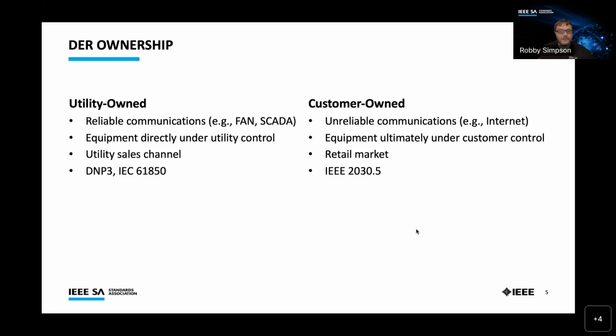And then lastly, the standards and protocols themselves. Usually with utility-owned equipment, often in the US you'll see DNP3. Often in other parts of the world you'll see IEC 61850. There tend to be these protocol standards that are specific for utility networks, for the utility use cases and the ways those operate. Whereas in the customer-owned world, the only one I'm aware of that covers this area is IEEE 2030.5.